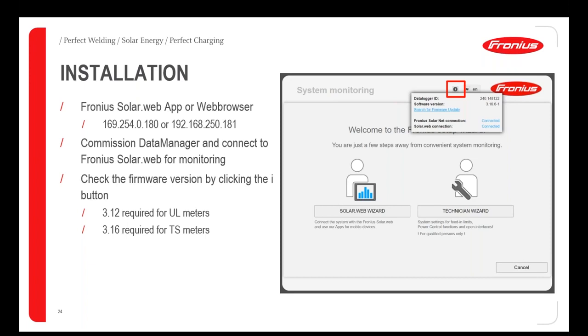Before we start that, it's very important to have a look at the software version of your data manager. This is a new smart meter, so we need to make sure that we're on the latest firmware version for your data manager. You can always check that from the little information button at the top of the screen. It will show the software version, and if that's below 3.16, we'd recommend you click on the search for firmware updates and automatically update your firmware to the latest version. Once you've done that, you'll be able to detect the smart meter and use the system.